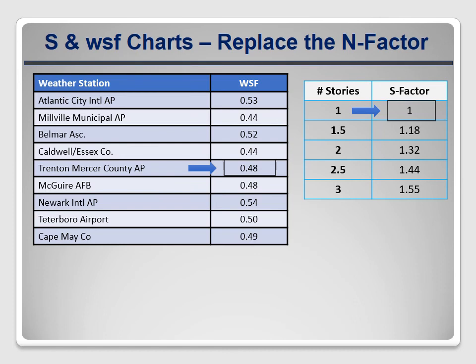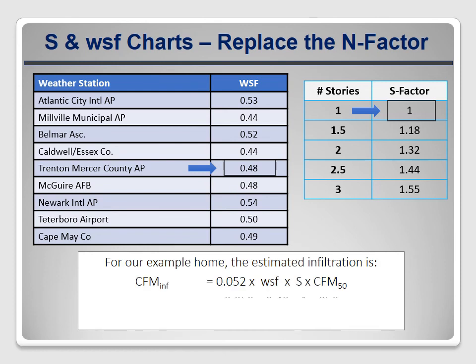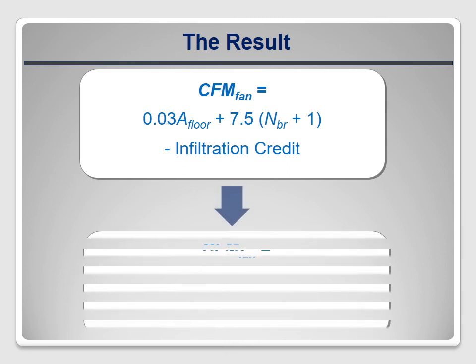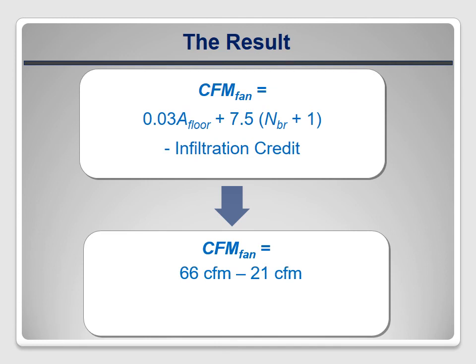Now we can plug those numbers into the equation. The estimated natural infiltration is 0.052 times the weather and shielding factor of 0.48, times the S factor of 1, times the blower door reading of 850 CFM. That gives us an estimate of 21 CFM — that's our infiltration credit. We now have all the pieces: the total desired ventilation rate of 66 CFM minus the infiltration credit of 21 CFM equals 45 CFM. We need to install a fan that can provide at least 45 CFM of continuous ventilation.